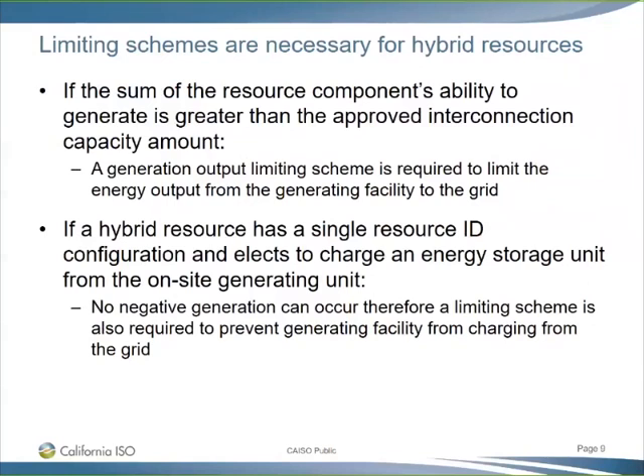First, if the sum of the resource components' generation capability is greater than the approved interconnection capability, then a generation output limiting scheme is required to limit that resource's output to its point of interconnection rights. This is similar to how it works for any oversized project today—we see oversized projects like VERs or solar farms that also have to have limiting equipment to ensure they don't go above their approved interconnection capability.